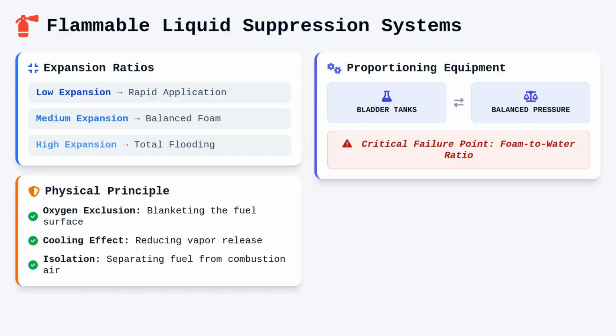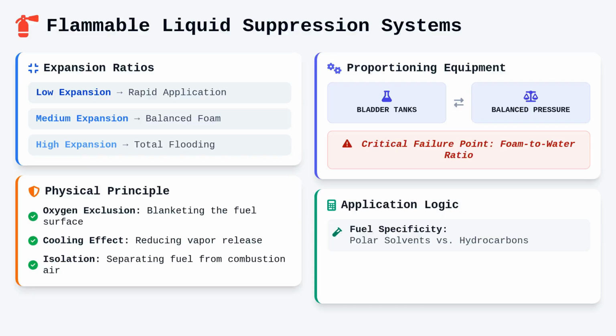You must calculate the application rate based on the specific fuel type, as polar solvents and hydrocarbons react differently to the chemical surfactants within the foam concentrate. The volume of foam generated must be sufficient to achieve total containment within the drainage path of the protected space, ensuring the fuel is physically isolated from the combustion air, regardless of spill size.